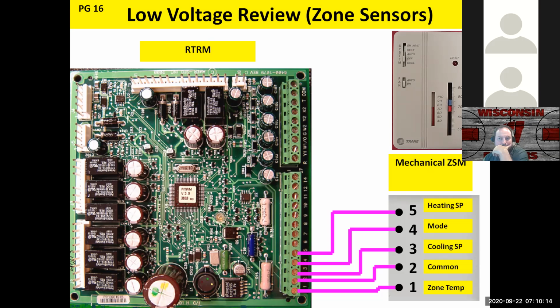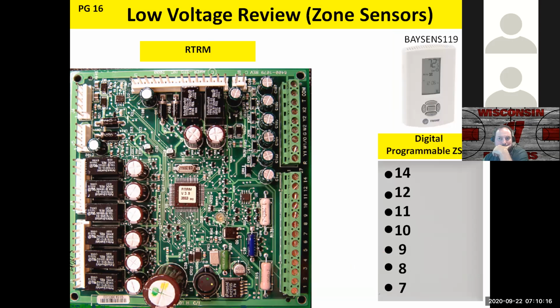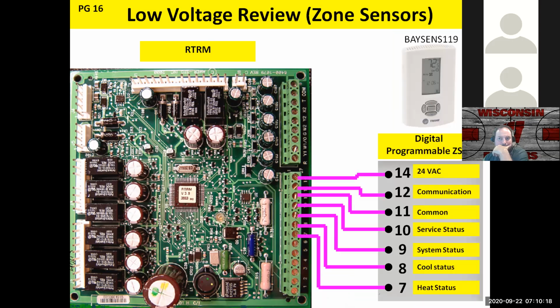Now, if you go to the next set of wires, 7 through 14, this is a 32-volt DC circuit. So what this does is it allows you to have some information, some LED lights, or in the case of this thermostat, it'll give you a cool fail, a heat fail, system status, and tell you if the fan's running. So 7, 8, 9, and 10 are basically information inputs to the thermostat.